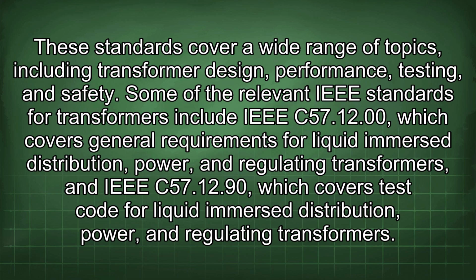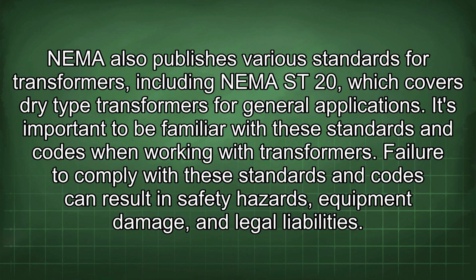Some of the relevant IEEE standards for transformers include IEEE C57.12.00, which covers general requirements for liquid-immersed distribution, power, and regulating transformers, and IEEE C57.12.90, which covers the test code for liquid-immersed distribution, power, and regulating transformers. NEMA also publishes various standards for transformers, including NEMA ST 20, which covers dry-type transformers for general applications.